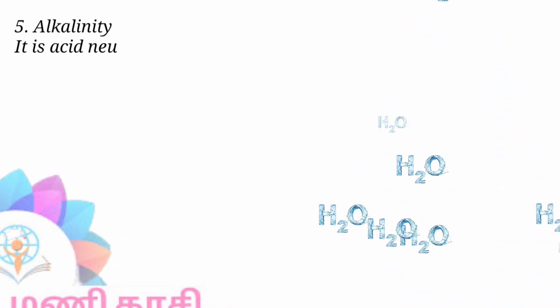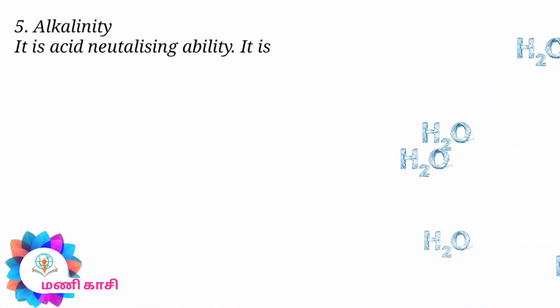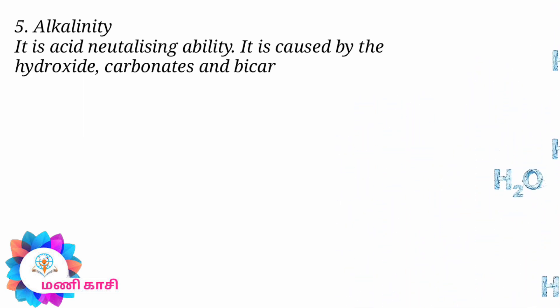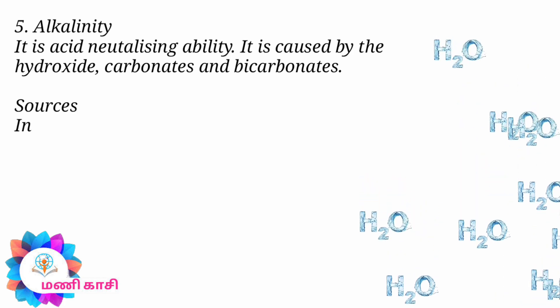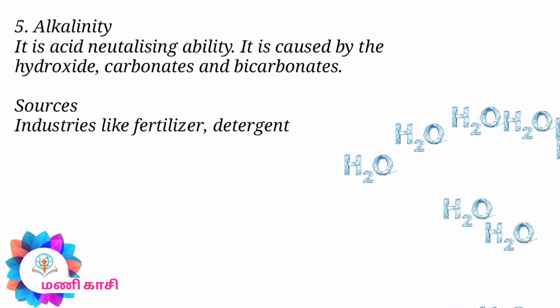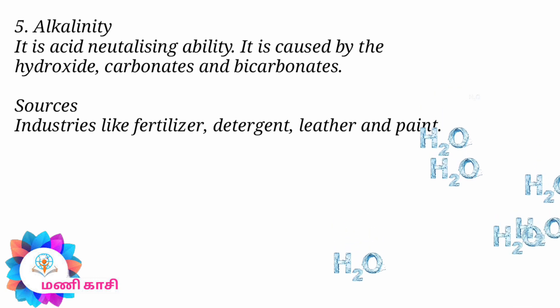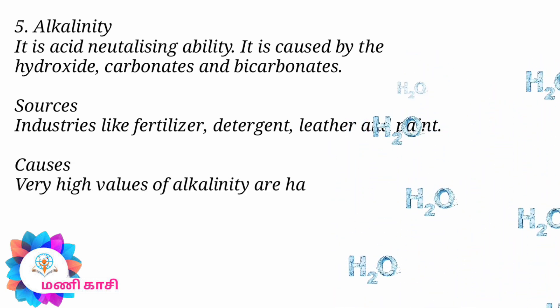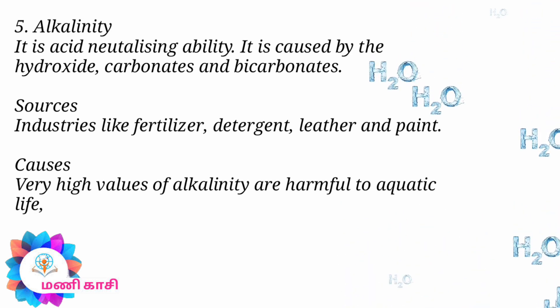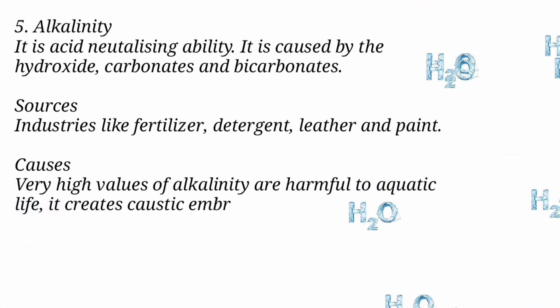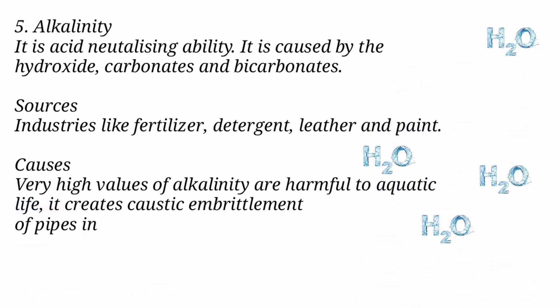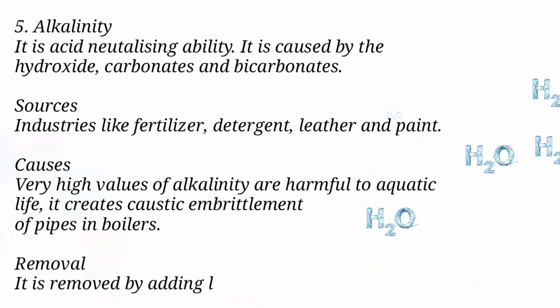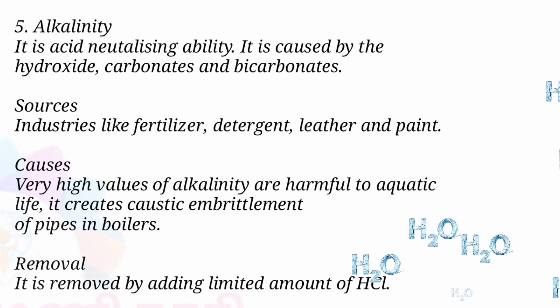Alkalinity is the acid-neutralizing ability of water, caused by the presence of hydroxide, carbonates, and bicarbonates. Sources include industries like fertilizer, detergent, leather, and paint. Very high values of alkalinity are harmful to aquatic life and create caustic embrittlement of pipes in boilers. Alkalinity is removed by adding a limited amount of HCl.